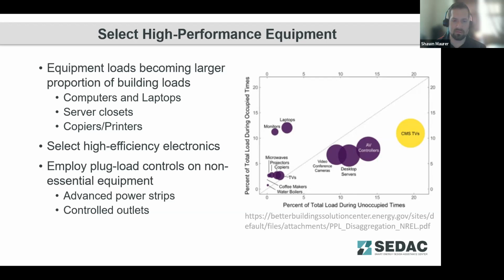Some other control strategies include advanced power strips. Those are coming with the newer versions of the 2021 IECC, have been in ASHRAE since the last code cycle, and controlled outlets as well, where now you've got some ability to turn off non-essential loads when occupants aren't in the space through an automated detection. So you're not relying on people to do optimization strategies. You've got a little more automation, a little more ability to make these fail safe.